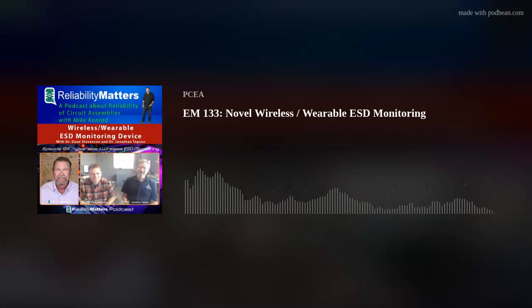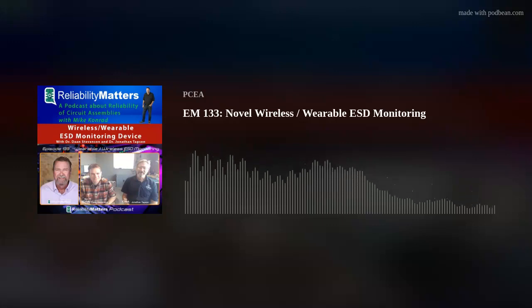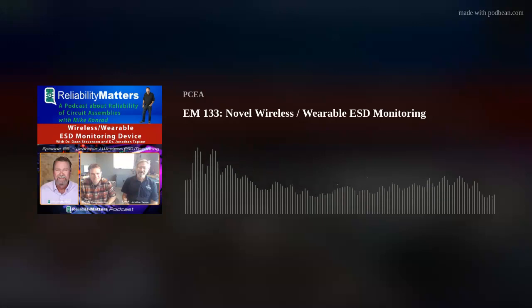And I'm seeing the person wearing this over an ESD smock. I'm assuming that you're not going to put it over your North Face jacket or something, right? This has to be mounted on something conductive. Yeah, that's a great insight. It needs to accurately represent the voltage of your skin, if you like. So an ESD shirt that makes electrical contact with your skin is good. Anything with a little bit of conductivity, or even something that doesn't generate charge. So as you say, a fleece from North Face would generate a bunch of charge. We all know, we've all had that experience. That wouldn't be practical. But a cotton shirt or a proper ESD garment is great.